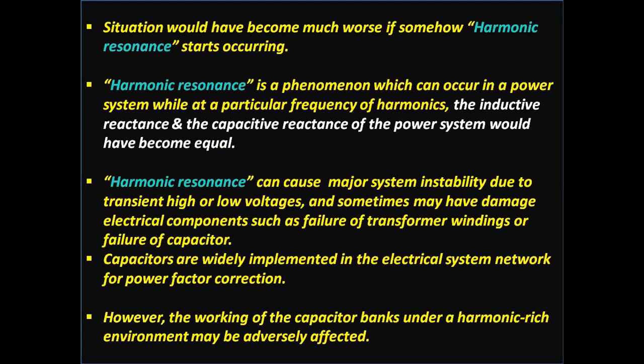The situation becomes much worse if harmonic resonance starts occurring. Harmonic resonance is a phenomenon which can occur in a power system when, at a particular harmonic frequency, the inductive reactance and the capacitive reactance of the power system become equal. Harmonic resonance can cause major system instability due to transient high or low voltages, and sometimes may damage electrical components, such as failure of transformer windings or failure of a capacitor.